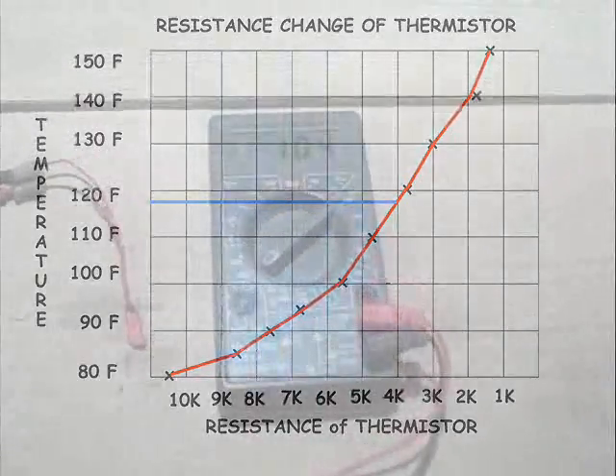Now the probe resistance is back to 10.4K. And that means, of course, that the temperature of the probe is what? That's right — it's a little more than 75 degrees Fahrenheit. It might be 76 or 77 degrees Fahrenheit.